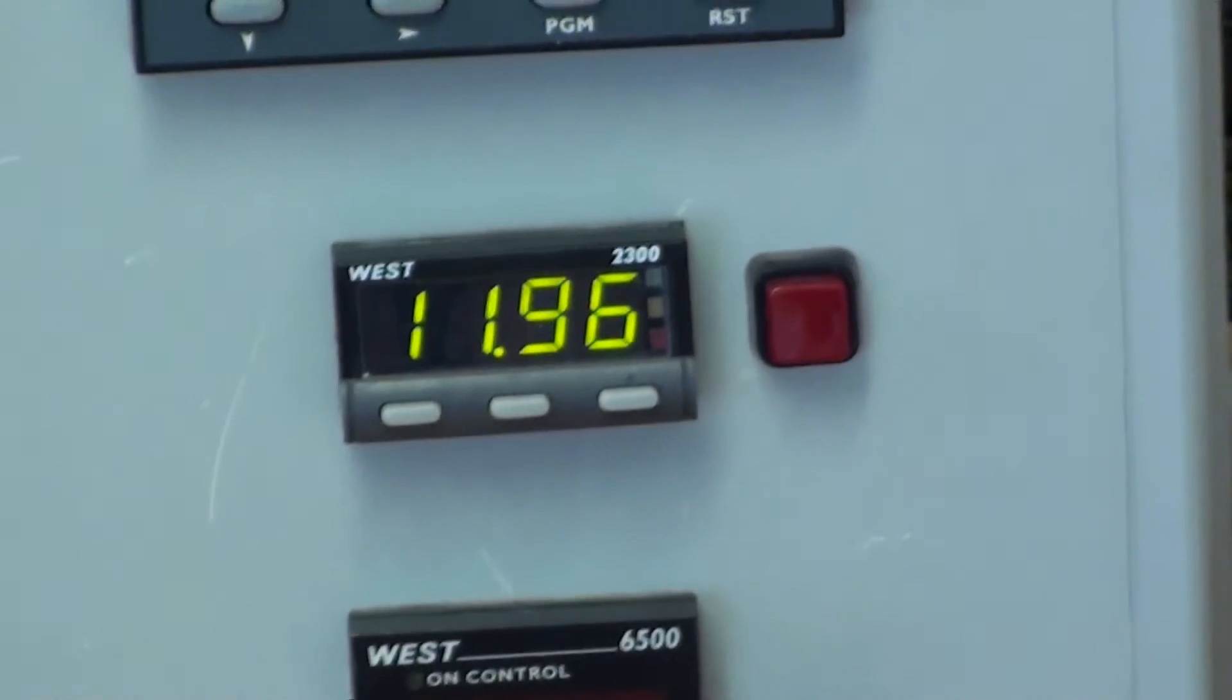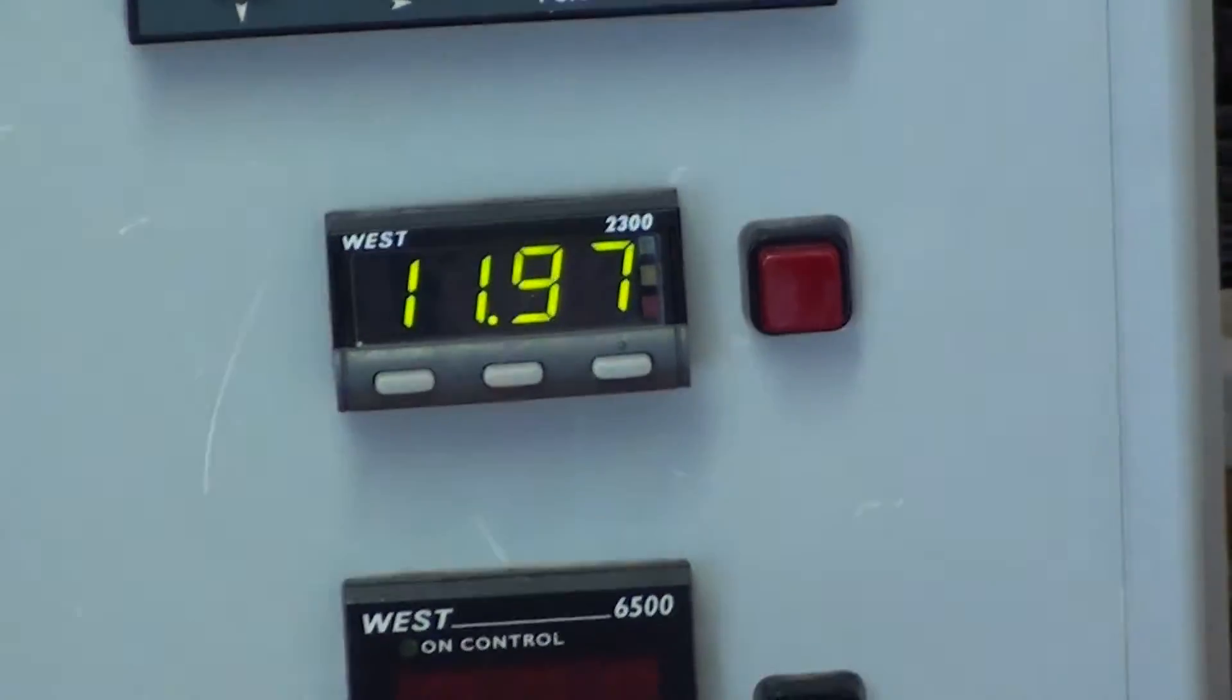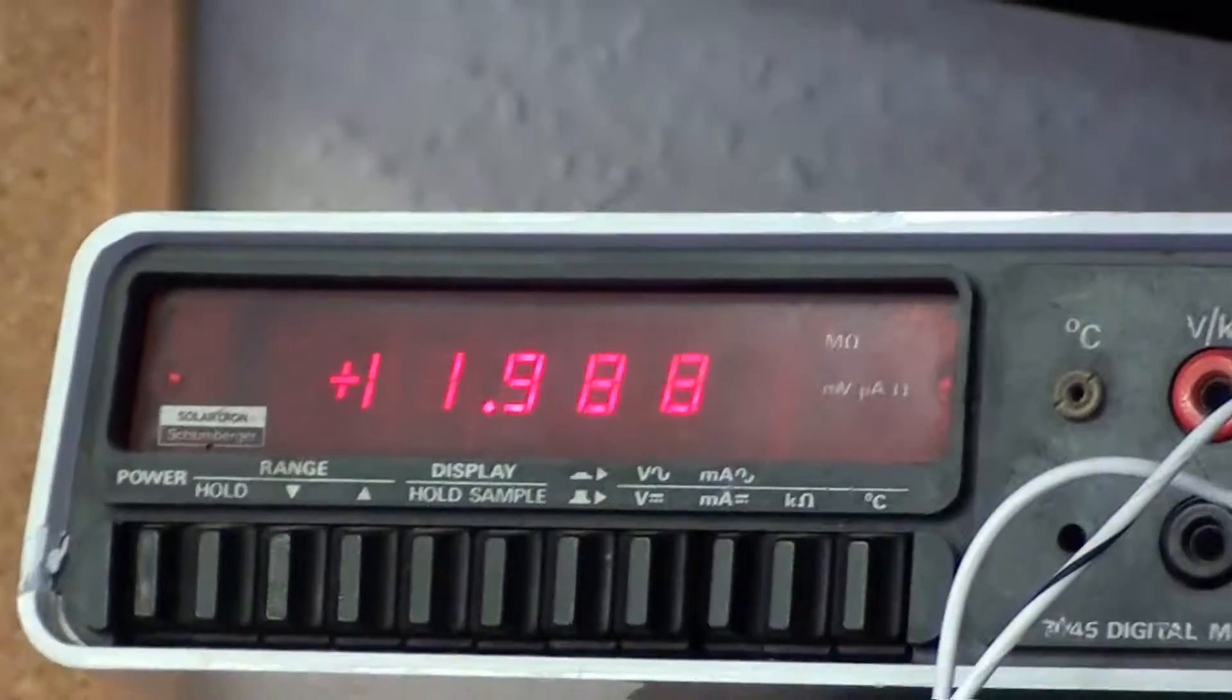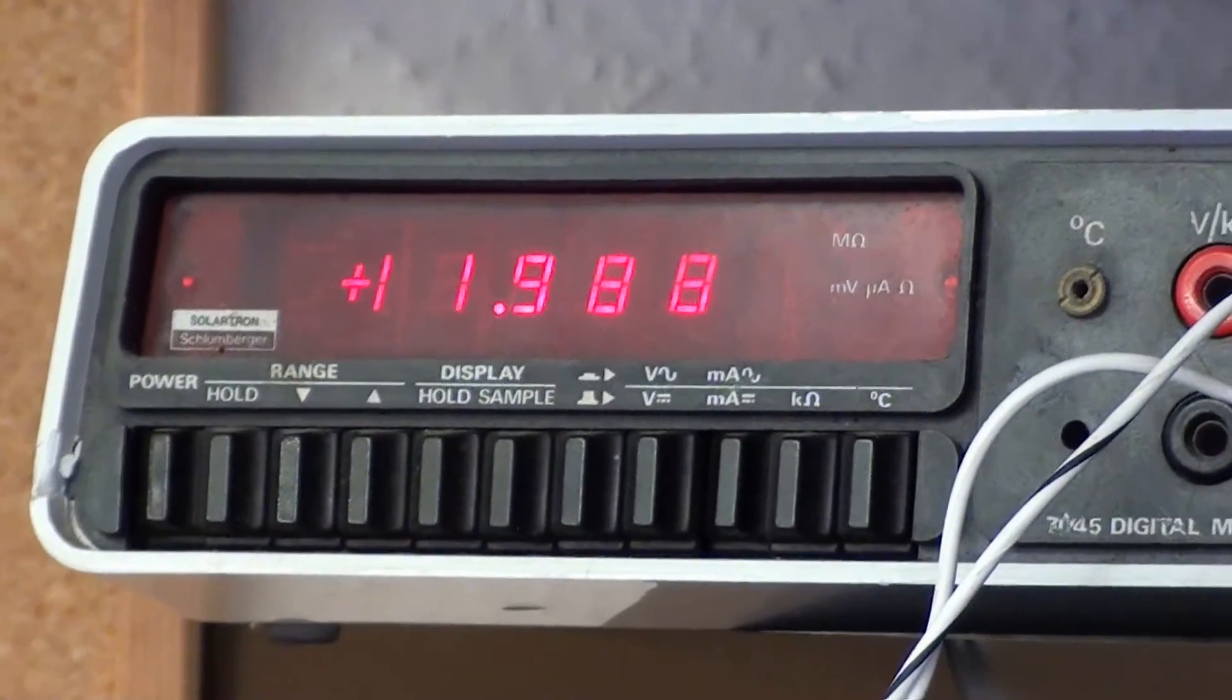The digital display on the indicator coming up to 12mA, and also on the multimeter, you can see it's coming up to 12mA, 11.988 at the moment.